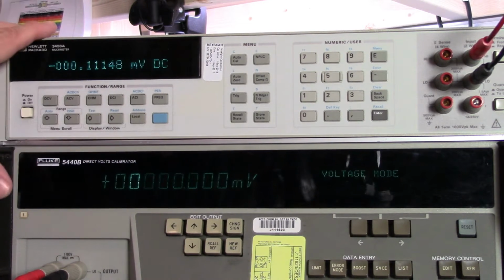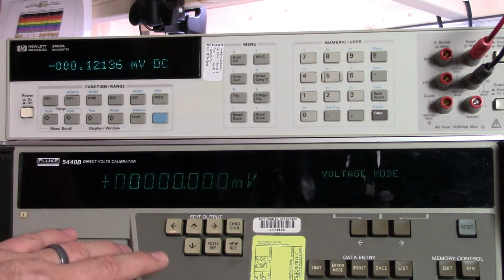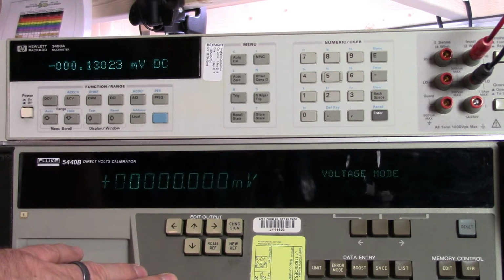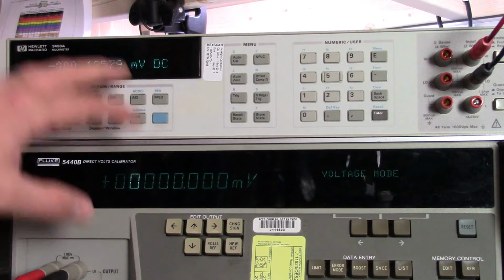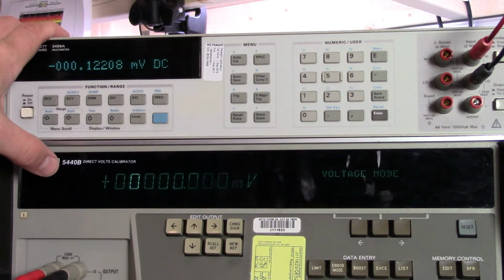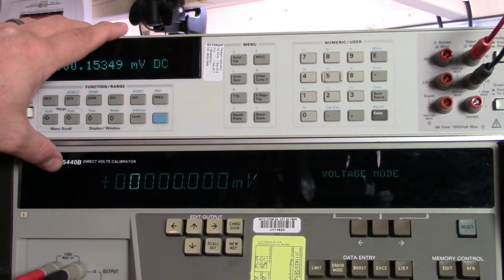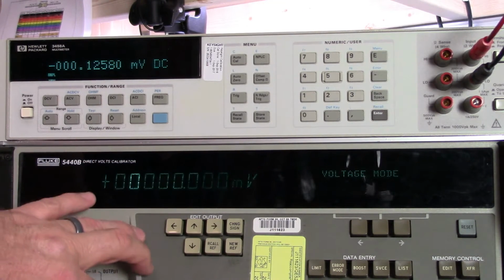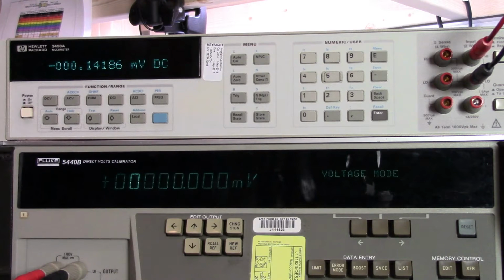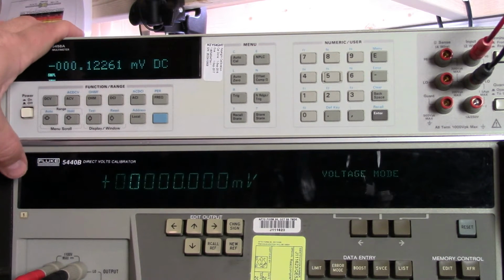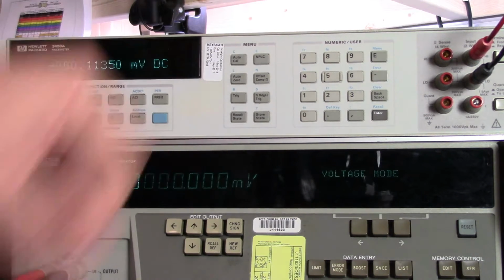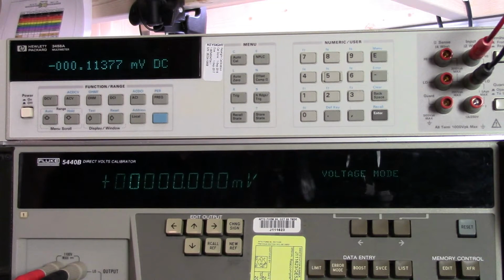Now, when I say bang on, we also need to put this in context: this has only been running for basically as long as the video has been going, and it has only just been turned on. So you're supposed to let these warm up. This one, according to the manual, you're supposed to give a 2-hour warm up and then run the auto calibration procedure. This one you're supposed to let warm up for an hour or so and then do the same thing, run the auto cal. Not going to do that, because I'm just intrigued to see how accurate things are just cold.